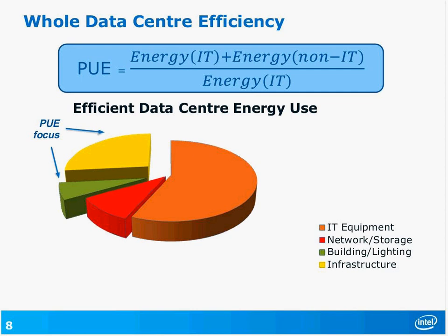If you've got a really large data center operator where IT is their factory, that is the product that they're producing, you might see a PUE of 1.1, 1.2 because they've wrung every single bit of inefficiency out of the system. The other thing to notice about PUE is because of the way it's constructed, it really ends up focusing in on your building and infrastructure. So it's really very facility oriented.